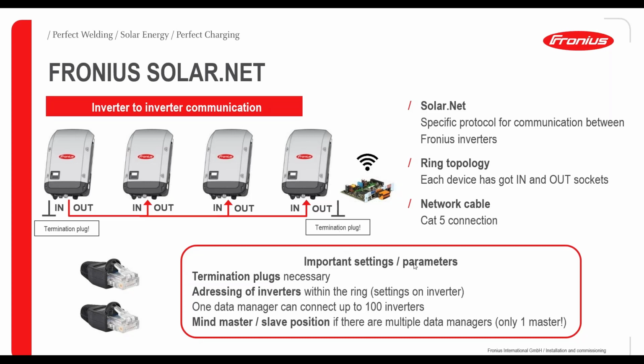Very important are the settings or parameters. As mentioned, set the termination plugs on the SolarNet ring and address the inverters - we need to address them so they understand each other, setting inverter 1, 2, 3, 4, and so on. We can have up to 100 inverters in such a ring topology, so one data manager can store data from 100 inverters. If we have, for example, 4 inverters each with a data manager inside, it's also possible to just switch off 3 of them.